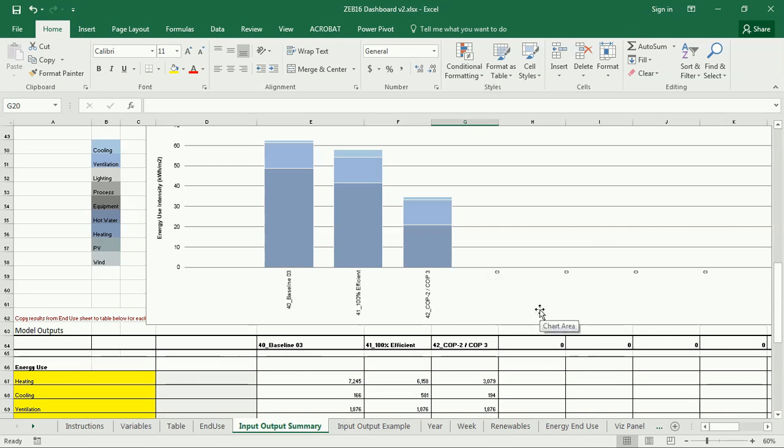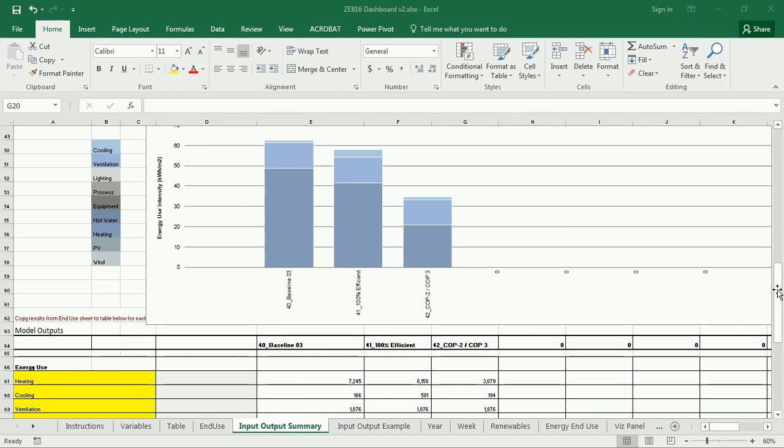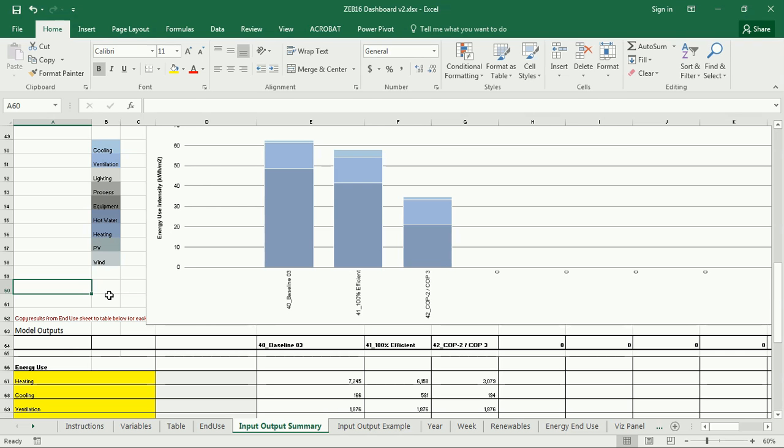And I should probably name this COP2, COP3 for heating and cooling. And you can see we've drastically reduced our heating and cooling. Now I should point out or remind you, I went over this earlier in an earlier tutorial on Energy Plus and HVAC systems. The one that we've modeled in Energy Plus is an ideal loads air system. So that means that it is going to supply as much heating or cooling energy as is needed in the zone in order to maintain the thermostat set points. And it's going to do so at 100% efficiency. So what we're doing here in the dashboard is accounting for different systems by using an effective coefficient of performance. Now this is a shorthand, a very quick way of estimating system performance. And in fact, Energy Plus can do quite detailed calculations for different systems. However, getting to learning those takes some time, and we don't have that much time left in the semester.